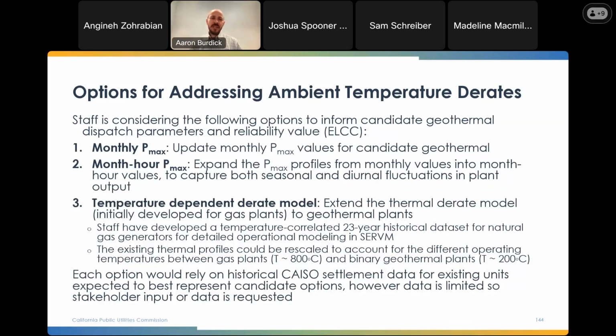We're considering three options in our models to capture this. The first is a monthly Pmax derate, reducing Pmax on a monthly basis to capture seasonal derates. The second is a month-hour profile for maximum output from candidate geothermal plants, capturing both seasonal and diurnal fluctuations in temperature and plant output. The third is a temperature-dependent derate model, which would, within SERVM, extend the ambient derate model developed for gas plants to geothermal power plants. Each option needs to rely on some historical data or model data for how to represent these candidate geothermal options.